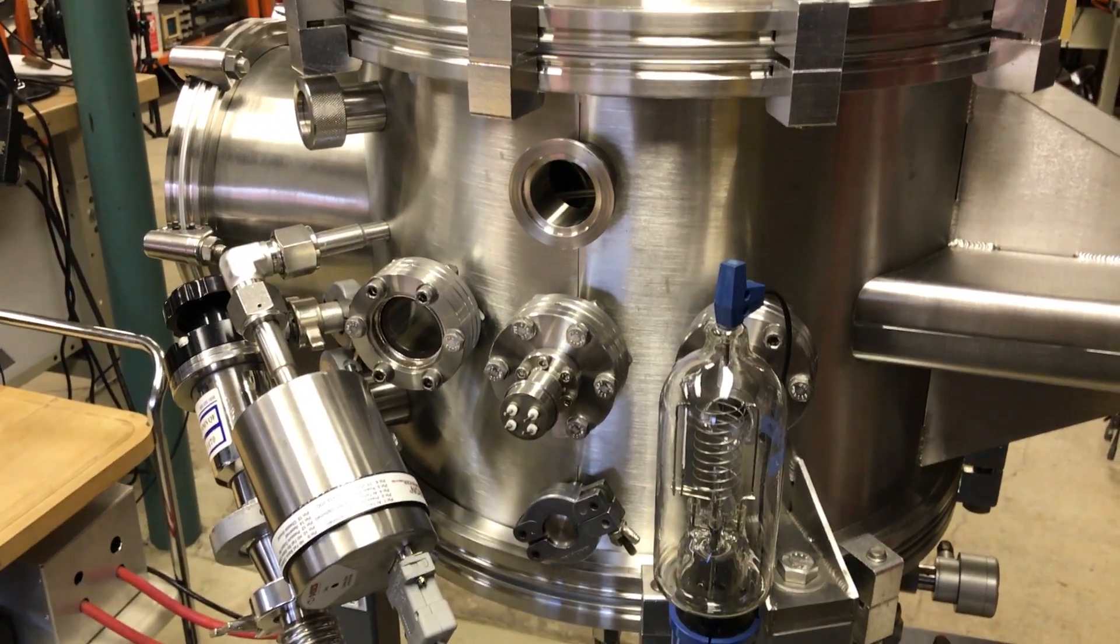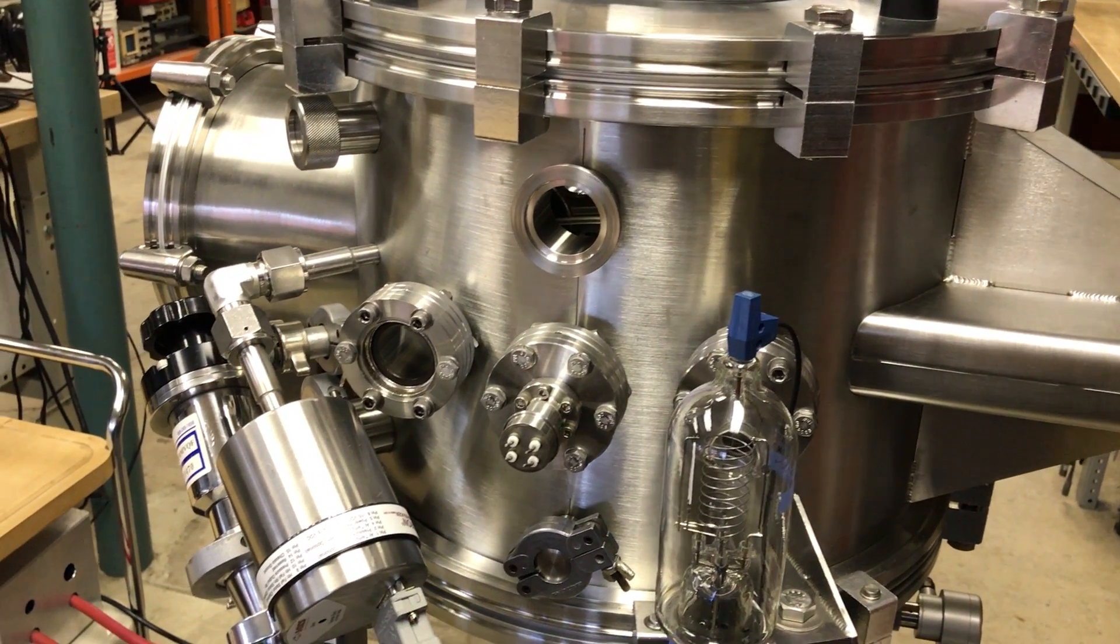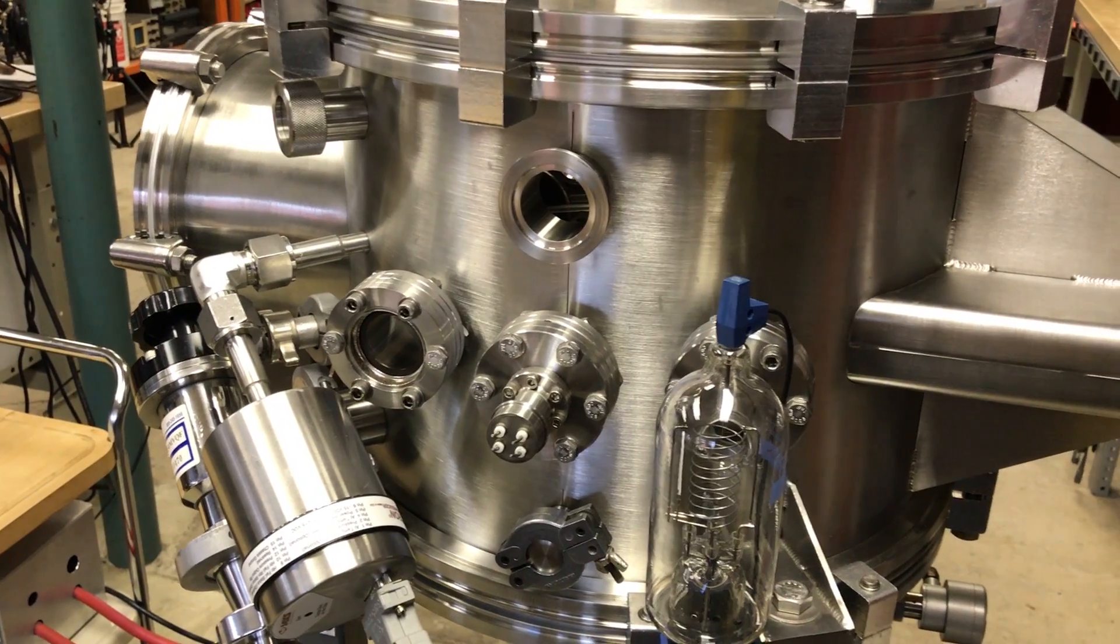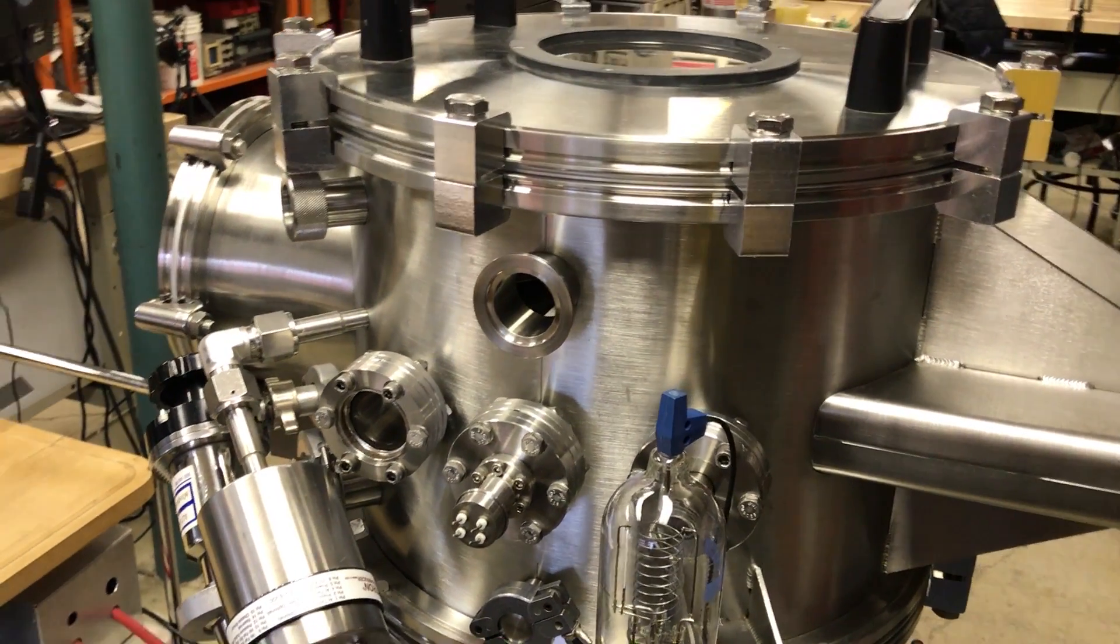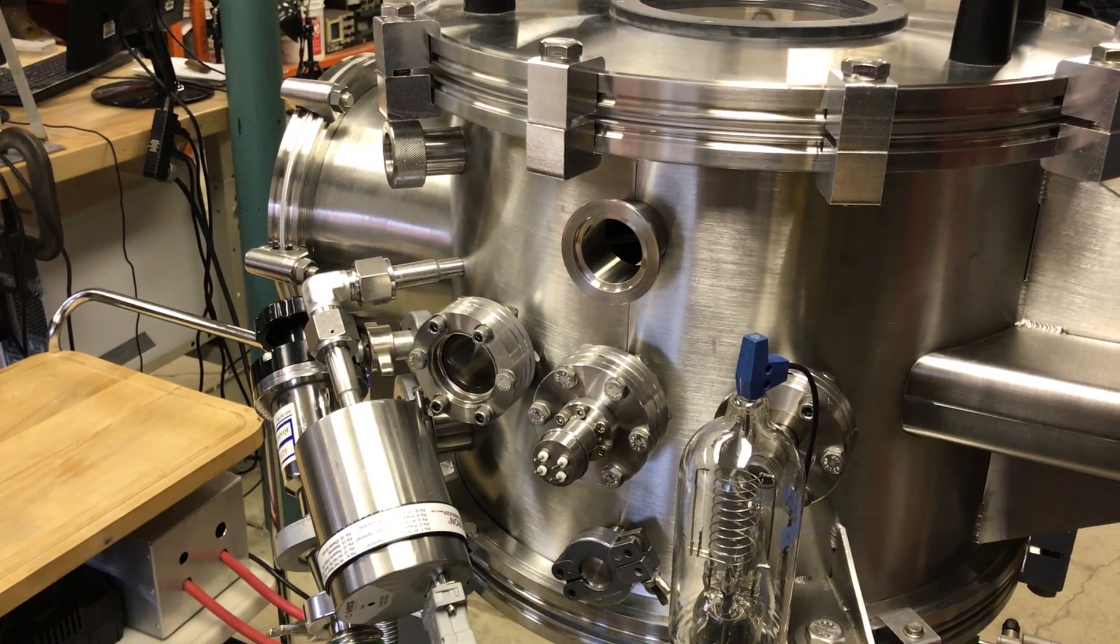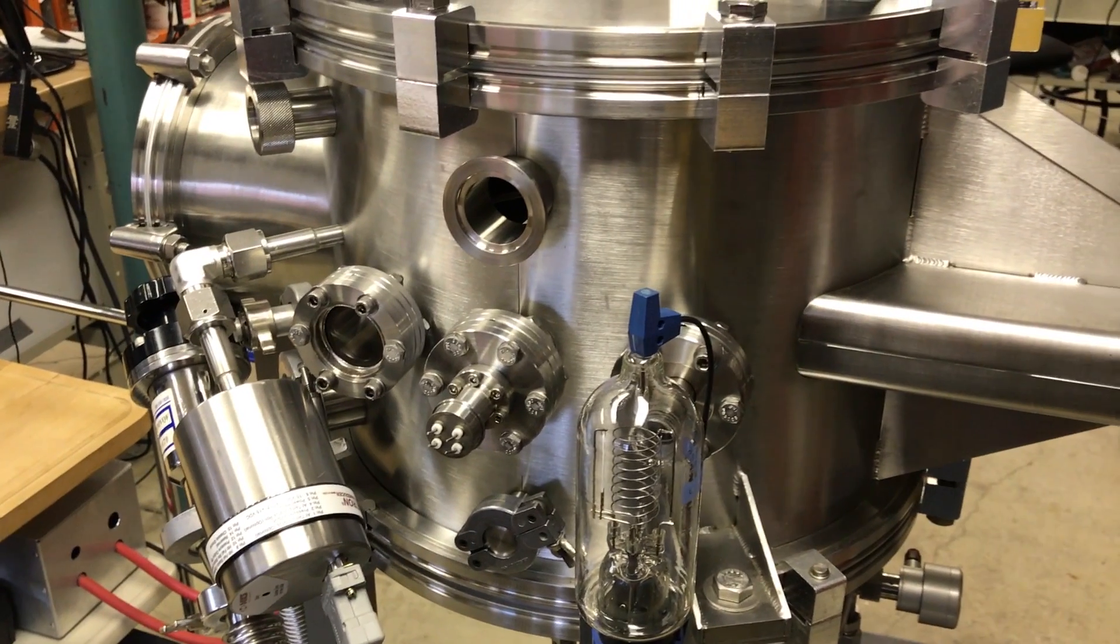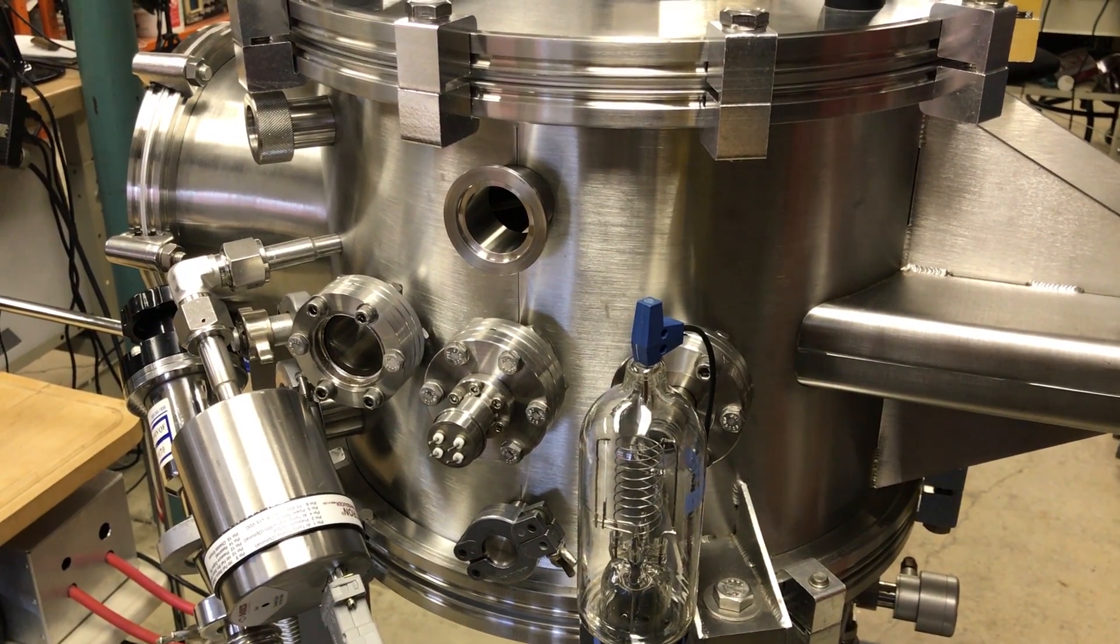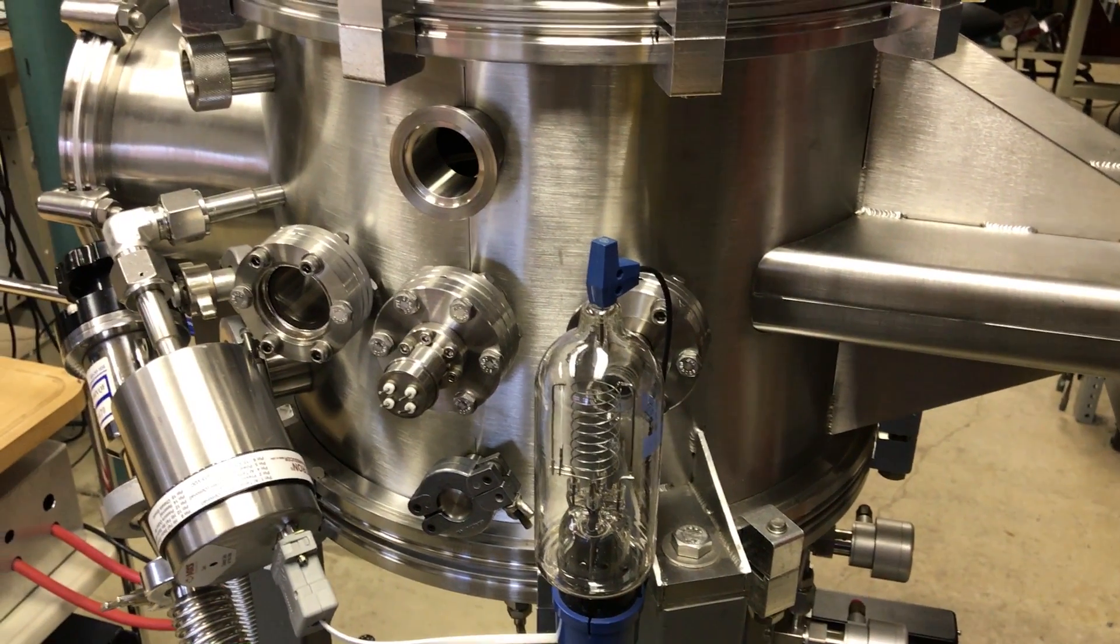Much like the vacuum pumps, it's important that you have multiple vacuum gauges as well. It's not as simple as you may think. So, I have three vacuum gauges on this chamber here, and they allow me to read anywhere from atmospheric, well, just below atmospheric pressure when I first turn my pump on, all the way down to ultra-high vacuum range.